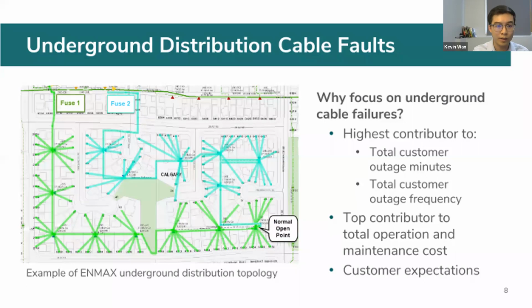And on the left-hand side of the slide, we have an example of the ENMAX underground distribution system, where we have highlighted two portions of an underground radial distribution loop in blue and green, and both have protective fuses upstream and also a common normal open point, so that if one side of the loop experiences a cable fault, the fault would be located by a crew, isolated, and then customers would be restored by closing the normal open point and replacing the fuse. And essentially here is where if multiple cable faults occur within a short amount of time before repairs are made, this is where we have longer outage durations, as repairs have to occur first.